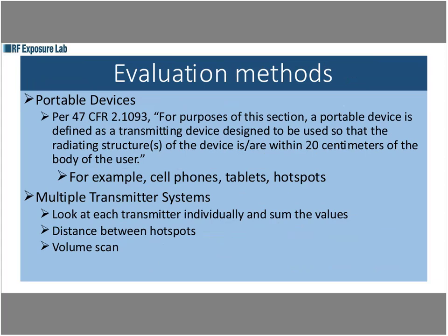Okay, so the evaluation methods. You've got portable devices, which, for the purpose of the section of 1093, a portable device is a device that is transmitting within 20 centimeters of the body of the user. Devices like this are cell phones, tablets, hotspots. A lot of medical devices are now falling into this, because many medical devices have wireless within the medical device itself. Implants, all of those types of devices, will fall under being a portable device.